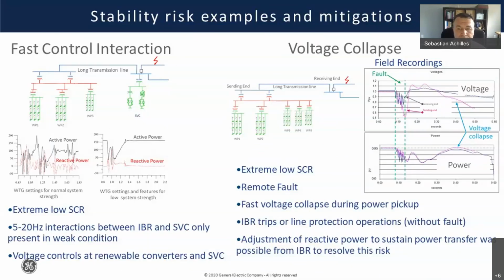This slide talks about examples of stability risks. There are two examples: on the left, the fast control interaction, and on the right, the voltage collapse. The one on the left shows, in the upper left, a simple one-line diagram with 3 wind plants connected through a long transmission line to a bus that has an SVC, with two outgoing lines to the rest of the utility system. There's a particular contingency where tripping one of those two lines makes the system extremely weak. In this case, the short circuit ratio was around 1.2.